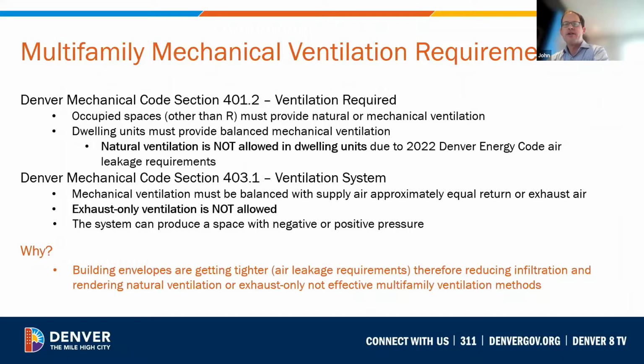Due to the Denver Energy Code air leakage requirements covered on the previous slide, the Denver Mechanical Code states that ventilation must be provided by mechanical means to all dwelling units regardless of building height. This means that dwelling units are not allowed to rely on natural ventilation via operable windows. One of the reasons why is that buildings have become increasingly airtight through construction practices, resulting in reduced air leakage, and the use of natural ventilation, especially on taller buildings, may impact the building pressurization.